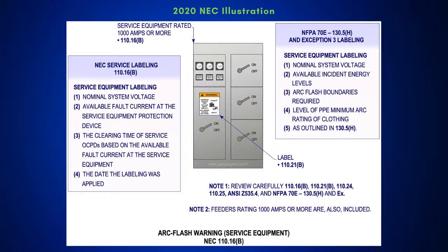When you look at this, you need to have the nominal system voltage and the available fault current at the service equipment protection device. We also need to know the clearing time of the service overcurrent protection device. And of course, that's based on the available fault current at that service equipment and the date the labeling was applied. Then if you look over on the right-hand side of the illustration, this is for equipment rated 1,000 amps or more. Now, if I look at 70E, on the right-hand side, we're going to tell you to look at 130.5(H) and Exception 3 for this. And we tell you there that you need the nominal system voltage, the available incident energy levels, the arc flash boundaries required, or it could be the level of PPE, minimum arc rating of clothing, and all this will be outlined in H here. And I'm going to show you all this in a minute.